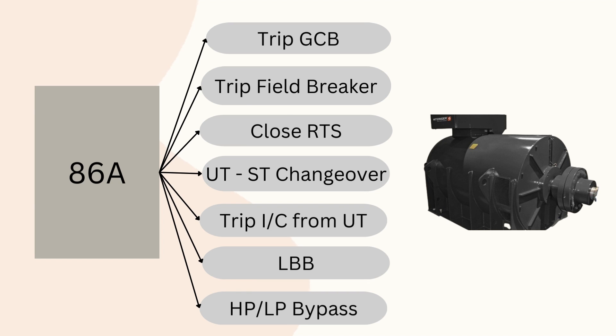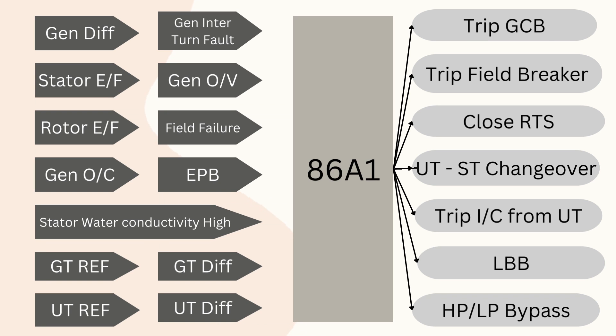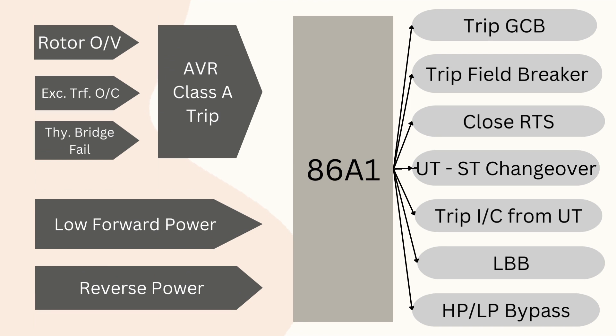In both Class A1 and A2, the trip command goes to all these locations. The 86A1 relay operates in fault conditions where immediate generator isolation is necessary to avoid damage. Similarly, the transformer should be isolated immediately when GT and UT REF and differential protections are operated. Critical protections of excitation systems requiring instant tripping, and conditions like low forward power and reverse power protection, come under Class A1 protection. Reverse power protection operates when the turbine trips, causing the generator to run as a synchronous motor and take power from the grid, damaging the generator and turbine.